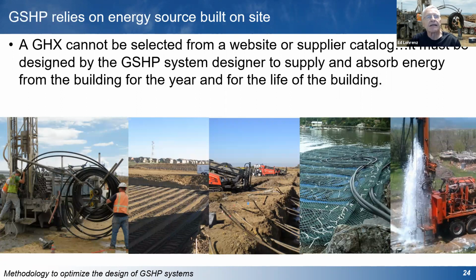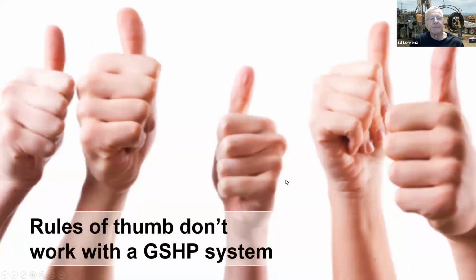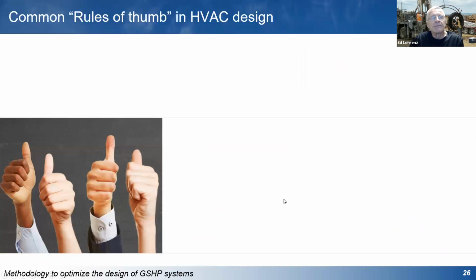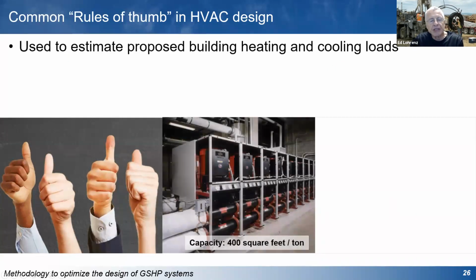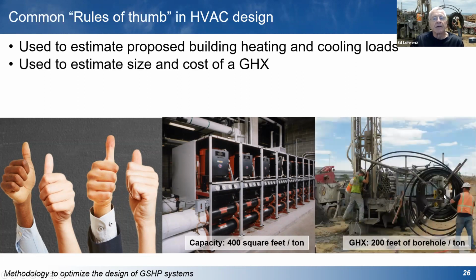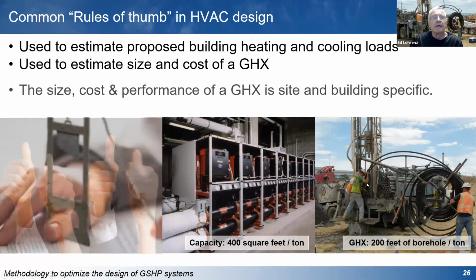You can't select a ground heat exchanger from a website or a supplier's catalog. You've got to actually design the system, and to do that, you really need to understand the energy loads. Rules of thumb are tempting to use, but they can really lead you astray. Some rules of thumb commonly used to determine the capacity of a heat pump system: 400 square feet per ton is a fairly commonly held number. For a 24,000 square foot building, you divide that by 400 square feet per ton, and you need about 60 tons of capacity. Ground heat exchanger, 200 feet per ton, and that's going to vary a bit from one region to another, but that's a fairly commonly used number, at least in the Minnesota and North Dakota area.